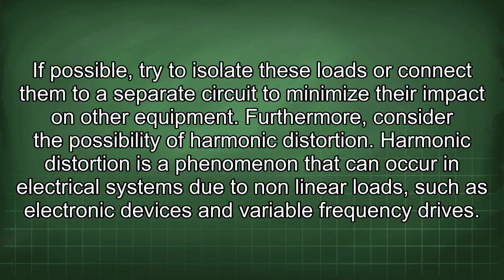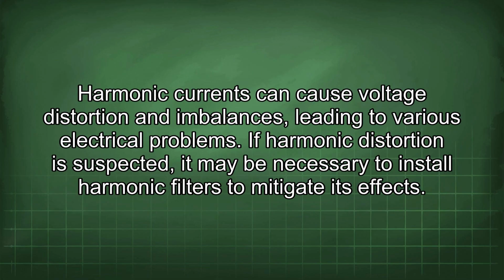Furthermore, consider the possibility of harmonic distortion. Harmonic distortion is a phenomenon that can occur in electrical systems due to nonlinear loads such as electronic devices and variable frequency drives. Harmonic currents can cause voltage distortion and imbalances, leading to various electrical problems. If harmonic distortion is suspected, it may be necessary to install harmonic filters to mitigate its effects.